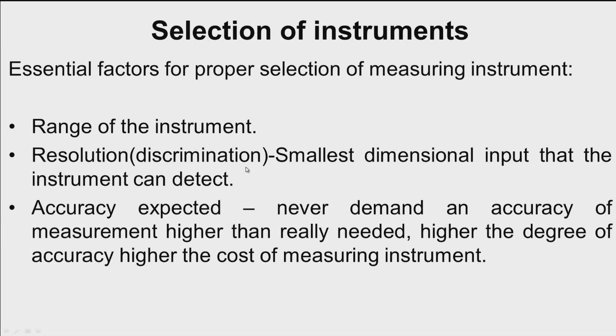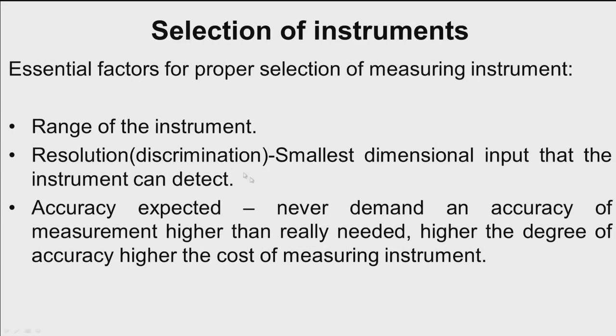Resolution or discrimination is the smallest dimensional input that the instrument can detect, and it depends on the accuracy level expected from the measurement process. If we need to measure a spindle's length to 0.001 millimeters, we should select an instrument capable of that. Regarding accuracy expected: never demand accuracy higher than really needed. The higher the degree of accuracy, the higher the cost of the measuring instrument.